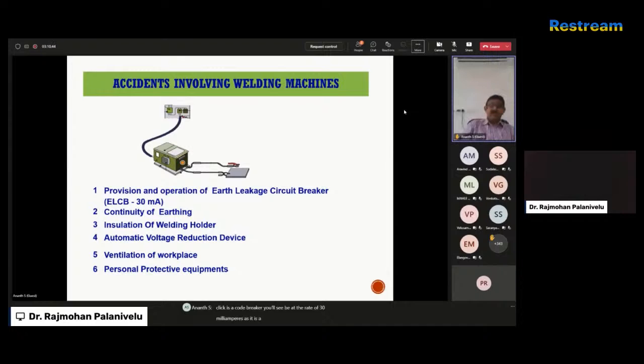it should be there on the mains, that is on the primary circuit, especially on the welding transformers. We can classify it into primary circuit and secondary circuit. So on the primary circuit, provision of this ELCB will prevent any electrical shock. But at the same time, on the secondary circuit, that is the power input from the transformer to the welding holder, we have to look at the voltage reduction device. Because if this inbuilt mechanism is already provided in the welding transformer, it's okay.